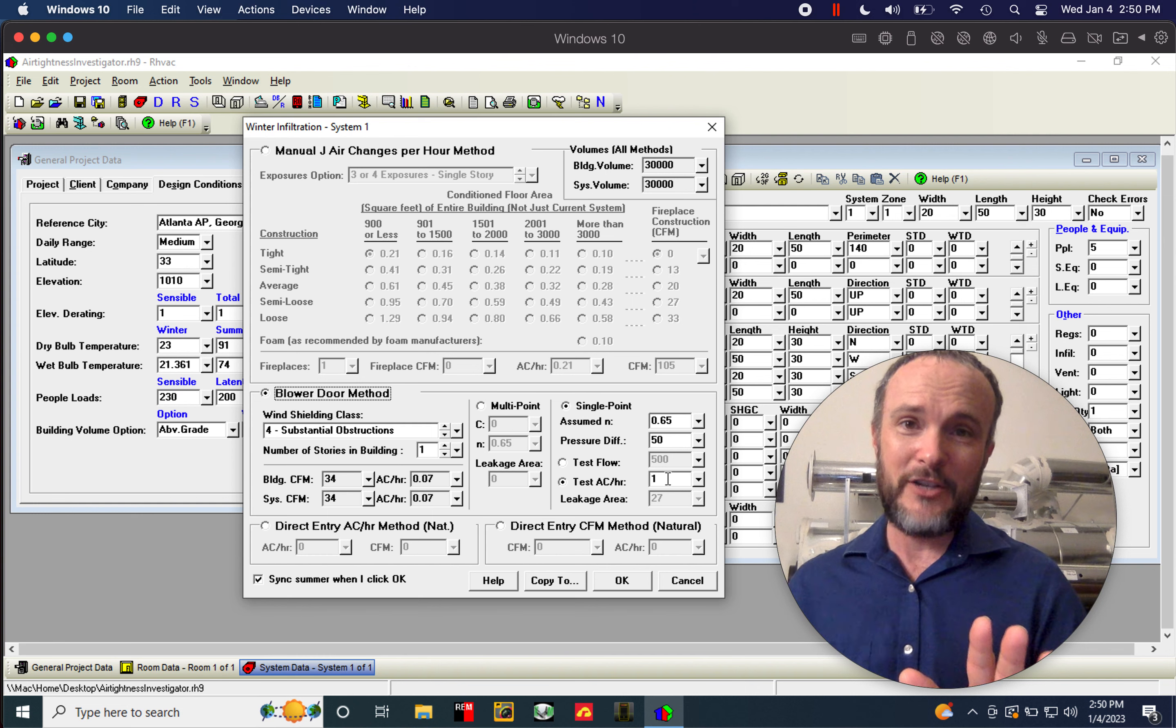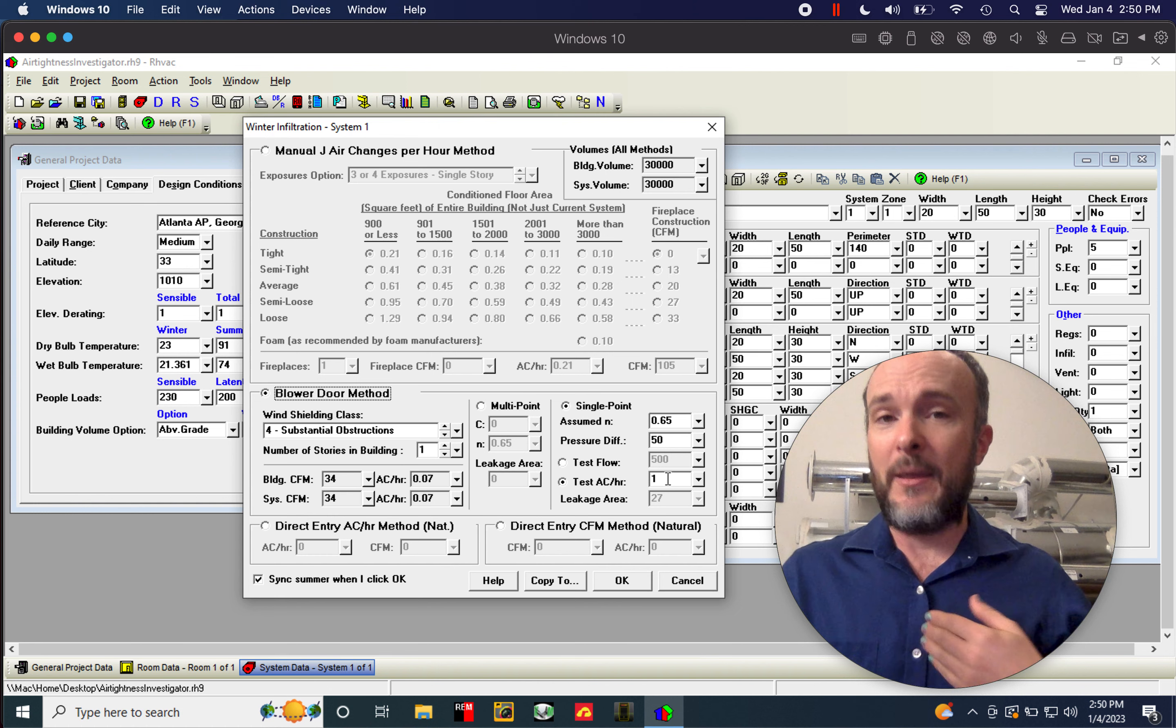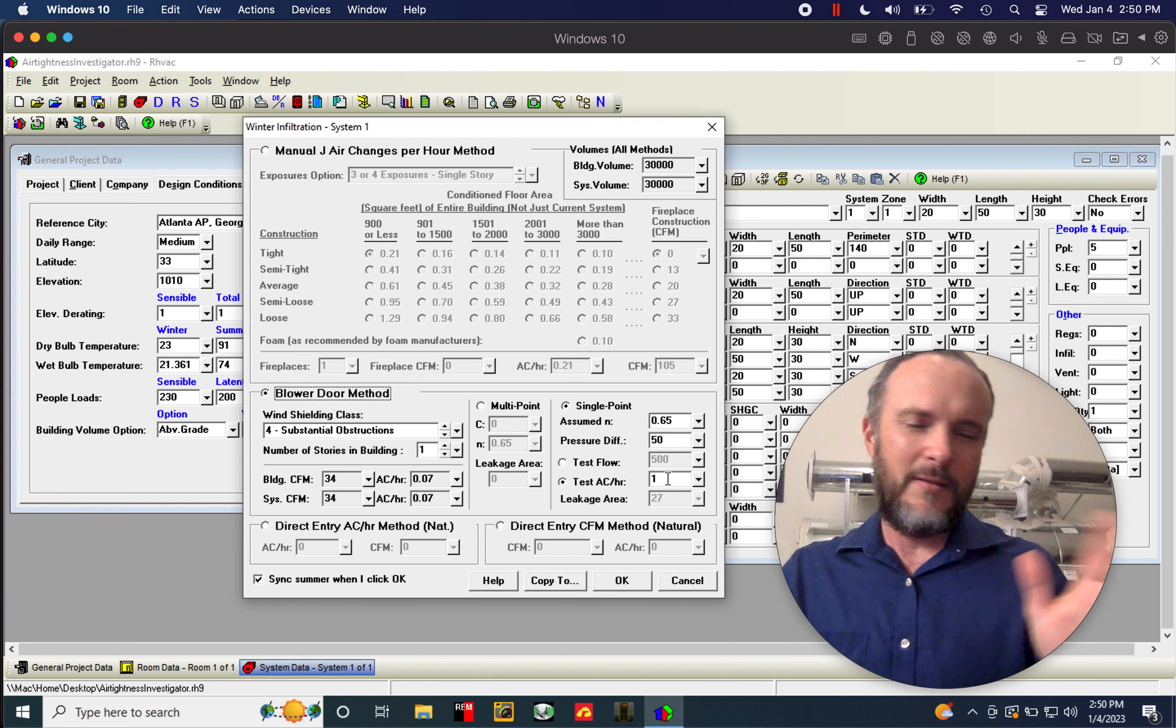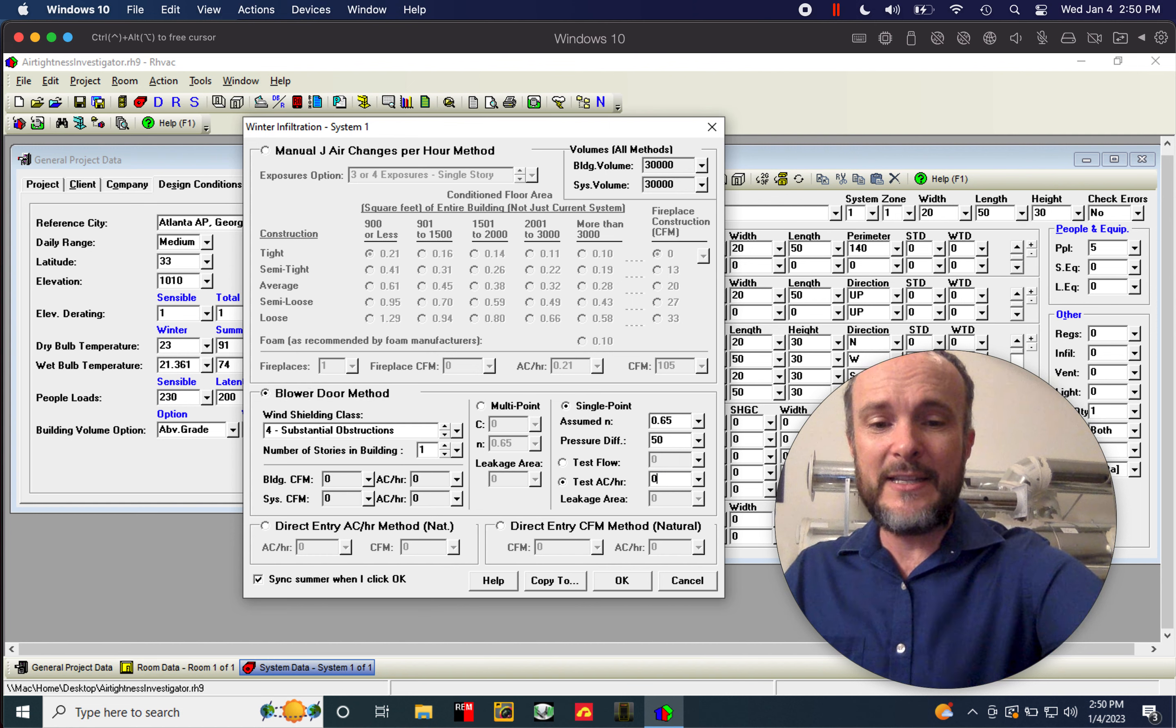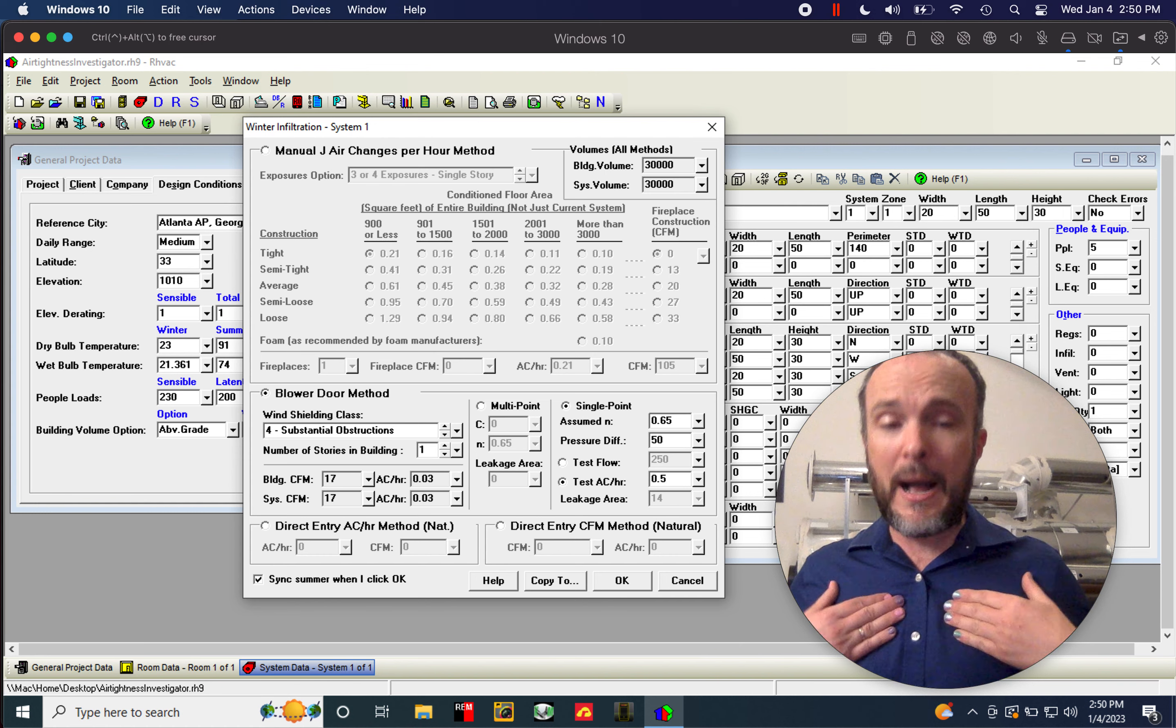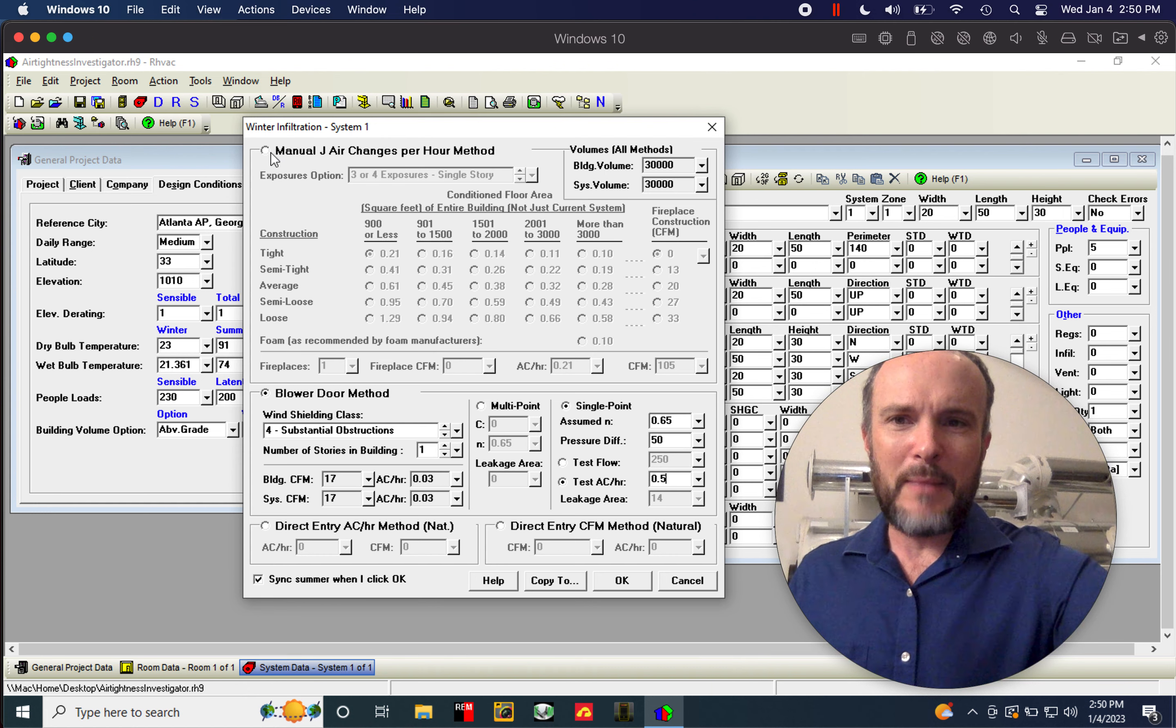That was what it was called yesterday by one of my clients. And I think that's a very nice thought. It a little bit offends me because what I really am doing is doing the math the right way, the basic right way, by just understanding all of this stuff. And it is not hard for HVAC guys to be understanding this. So that's why I'm making videos like this. Now, the test air changes per hour that my clients are typically shooting for because they're really chasing after energy efficiency and air tightness and comfort and health and noise control and all the things that are done by getting really airtight homes are one air change per hour or even 0.5 air changes per hour.